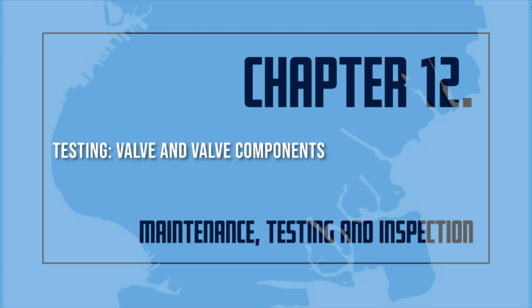6. When clean water flows, the test is terminated by closing the system control valve. 7. The air or nitrogen pressure and the time elapsed are to be recorded as follows. A. From the complete opening of the test valve to the tripping of the valve. B. From the complete opening of the inspector's valve to the start of a steady flow from the test connection. 8. All low point drains are opened and then closed when water ceases to flow. The dry pipe valve and quick opening are reset, if installed, in accordance with the manufacturer's instruction, and the system is returned to service.